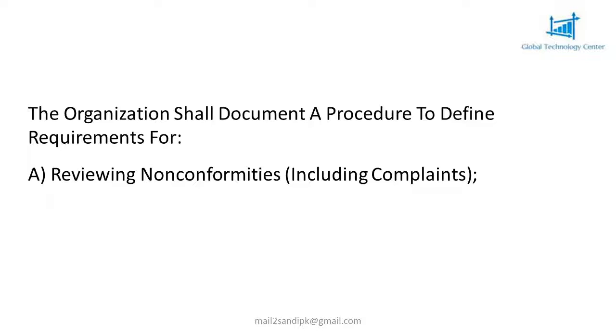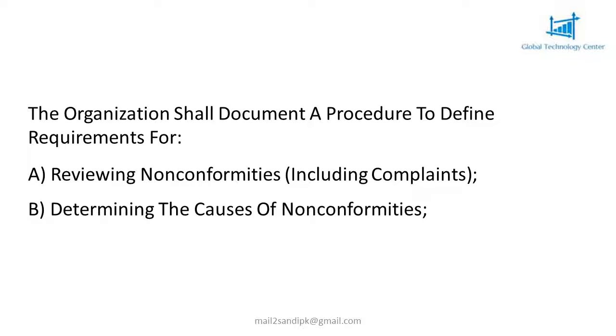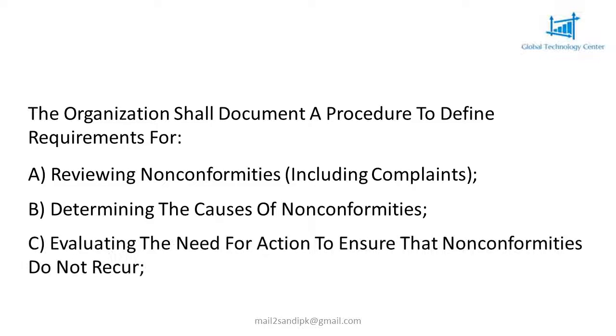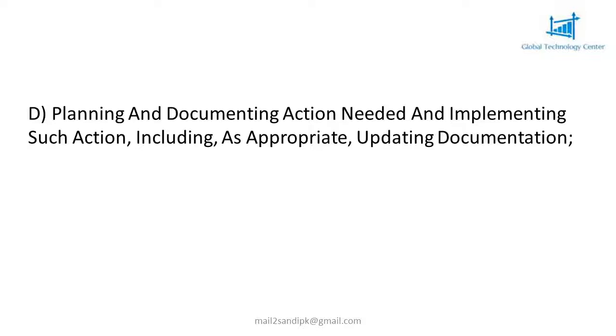A. Reviewing nonconformities, including complaints. B. Determining the causes of nonconformities. C. Evaluating the need for action to ensure that nonconformities do not recur. D. Planning and documenting action needed and implementing such action, including, as appropriate, updating documentation.